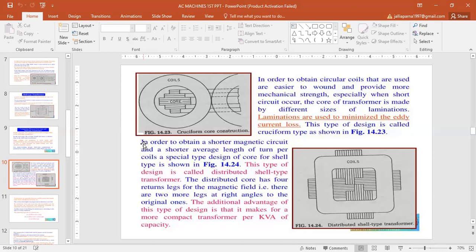In order to obtain circular coils that are easier to wound and provide more mechanical strength, especially when a short circuit occurs, the core of the transformer is made by different sizes of laminations. Laminations are used to minimize the eddy current losses. This type of design is called cruciform type. So in figure 14.23, the cruciform core construction. This is called cruciform construction.